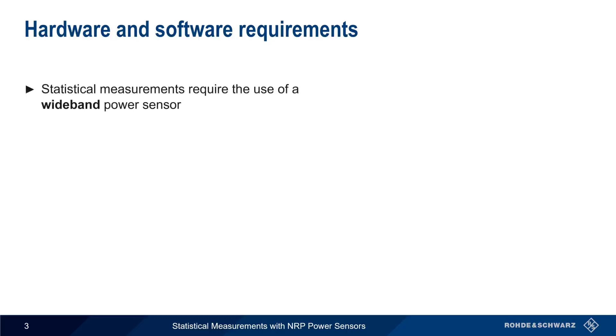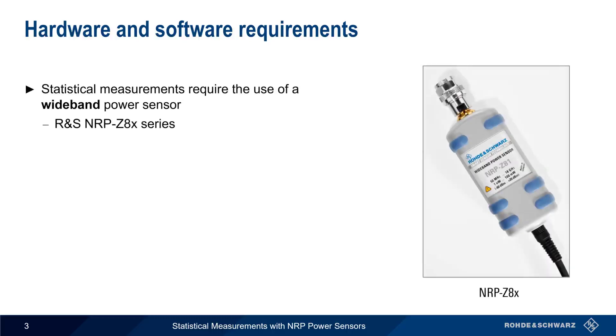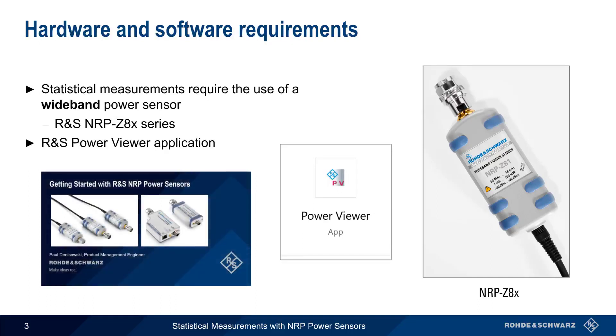Statistical measurements require the use of so-called Wideband Power Sensors, such as NRP-Z8X series sensors. In this presentation, we'll be configuring the sensor and collecting statistics using the PowerViewer software application. If you're unsure about how to install or use PowerViewer, step-by-step instructions can be found in the presentation Getting Started with Rohde & Schwarz NRP Power Sensors.